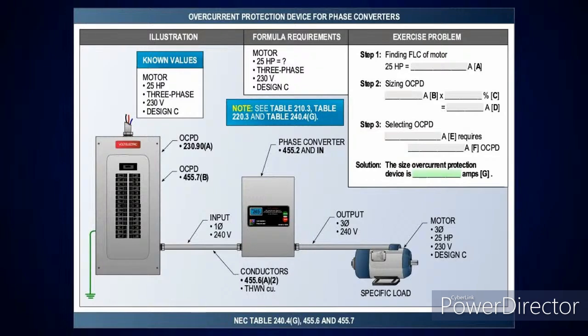Like this in here, this is simple. I just know what I'm looking at here. I know I've got to get the amperage, and I'm sizing an overcurrent device, so I know I have to use one of the tables. If I was doing overload, I know I need the nameplate. So I'll just get the amperage here. And based off what you just learned, we've got a fixed load here. It's a specific load. So I'm going to put 250% on here. And you just sort of learn the sections.